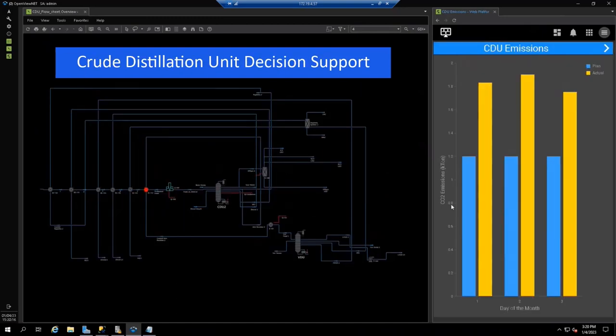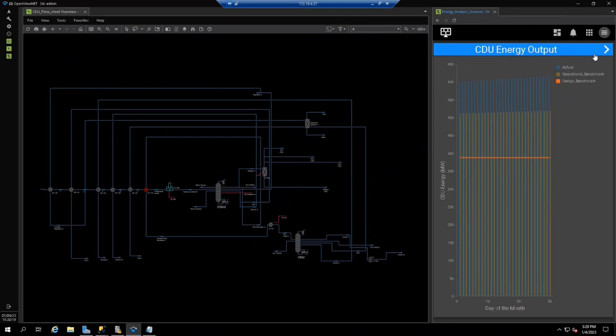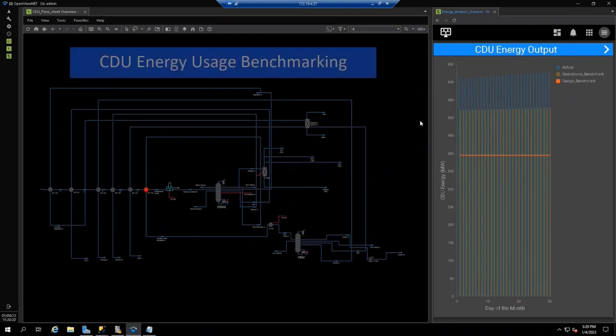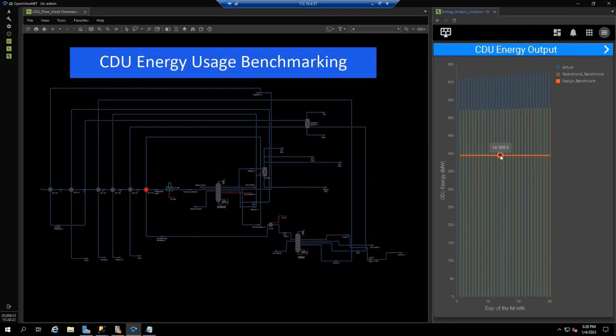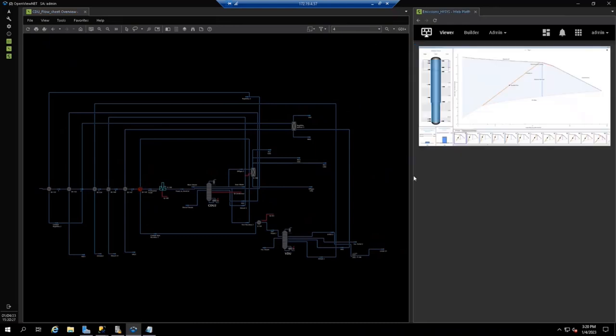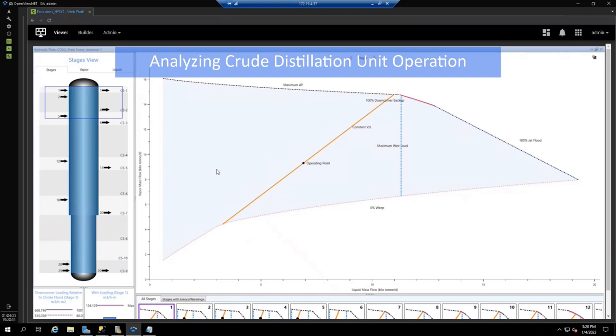Now we turn to the crude units, where a similar drill-down shows that actual emission levels in the CDU are also higher than the plan. In this case, there is also a higher energy consumption than the benchmark. The cause could be poor hydraulic performance at the distillation units or fouling in the pre-heat heat exchanger train. We can quickly look at both with this solution.